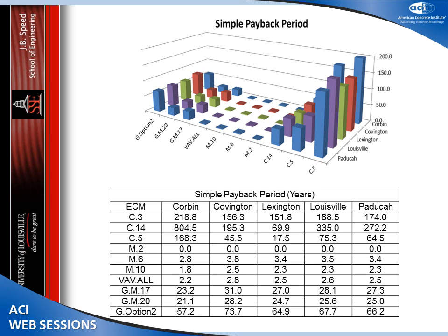We were getting very, very low paybacks in the mechanical area, where we combined the VAV all, okay, when we looked at the entirety of that, we got almost 60% reduction in energy, and our goal with our mandate by our state governor was 25% reduction. We were more than meeting that with paybacks well below 2 years.